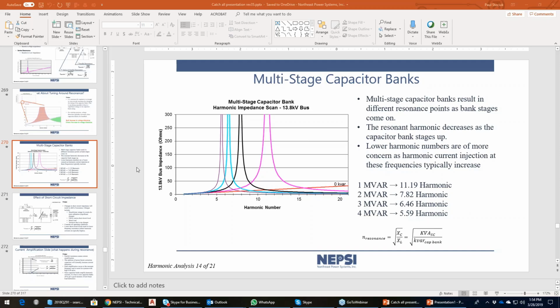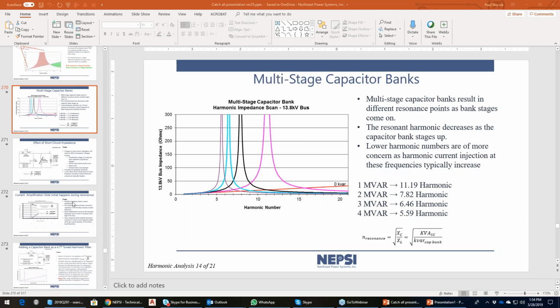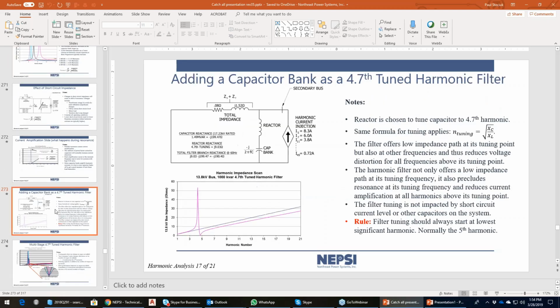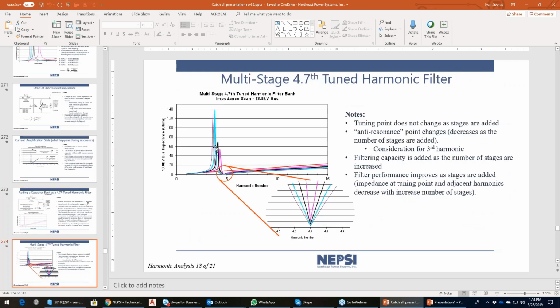So when you install a capacitor bank, you can expect to get resonance at frequencies that start at a higher harmonic and then work their way down towards lower harmonics. When you install a filter bank, normally that filter bank is tuned to a frequency, and you get an impedance curve similar to this. For a multi-tuned filter bank, you get a series of impedance curves, but as you can see here, the tuning point, in this case 4.7, has been pegged at that point. It does not move no matter what size capacitors I bring on, whether it's 1 Mvar, 2, 3, or 4 Mvar worth of reactive power. That 4.7 filter, the impedance at that point basically remains close to 0 ohms.